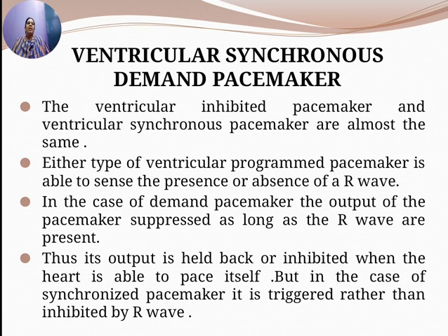In the case of a demand pacemaker, the output of the pacemaker is suppressed as long as R waves are present. If the R wave is not present, then it begins to work. Thus, its output is held back, which is the other word for inhibited, when the heart is able to pace itself. But in the case of a synchronous pacemaker, it is triggered rather than inhibited by the R wave.